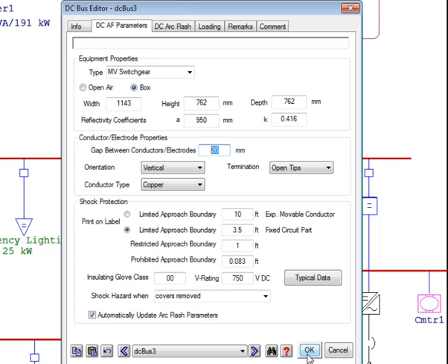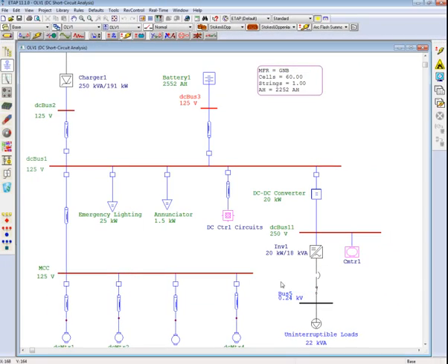If the gap were to exceed a certain distance, it is possible that there may not be enough voltage for the arc to occur or sustain. Therefore, there would not be a true arc flash hazard due to the fact that there would be too much distance between the conductors. Let's proceed to run an arc flash analysis utilizing the Stokes and Oppenlander method.